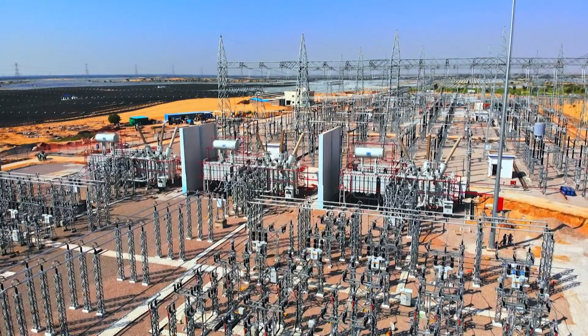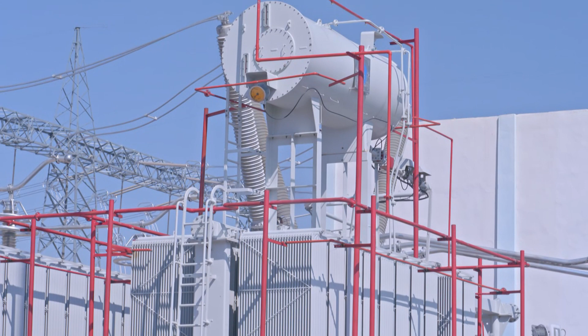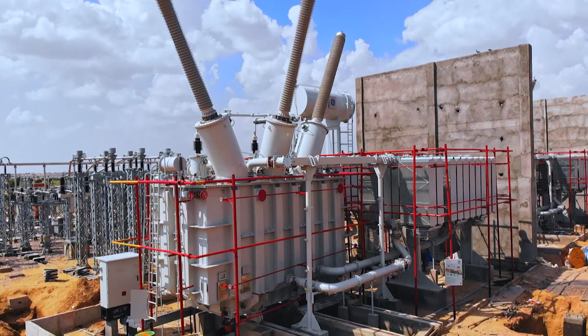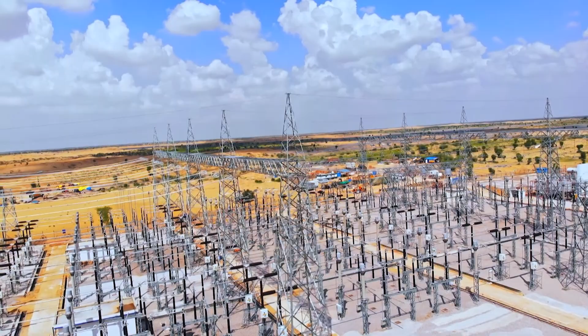All the current coming from the inverters is fed to the transformer for the step-up process. From the transformer, the stepped-up current goes to incoming and outgoing panels. Once power is collected at 33 kV, we increase the voltage to 400 kV by these 7 transformers. And these 7 transformers, once they boost the voltage at 400 kV, we collect them in a common bus. Bus means this is something in which all 7 transformers are connected in a common way. So all the 7 transformers pool power to a particular bus, and from here the power is evacuated to a power grid substation through an overhead transmission line.